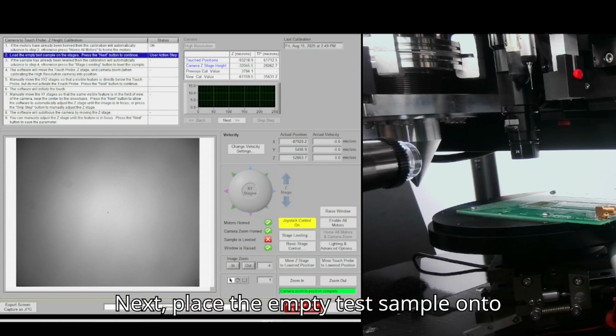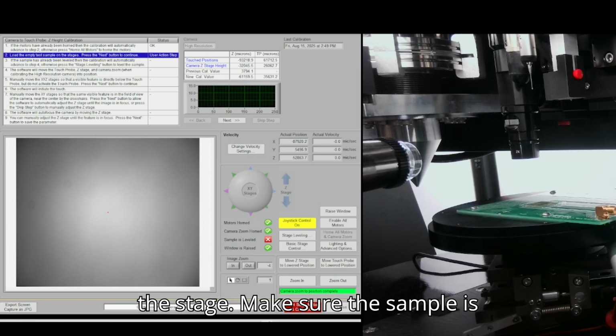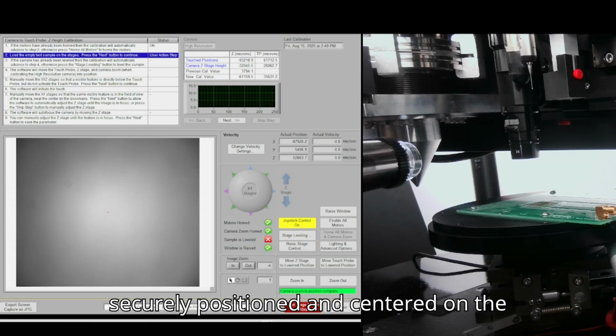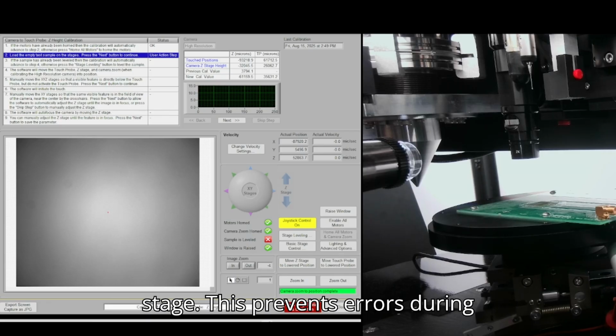Next, place the empty test sample onto the stage. Make sure the sample is securely positioned and centered on the stage. This prevents errors during alignment and measurement.